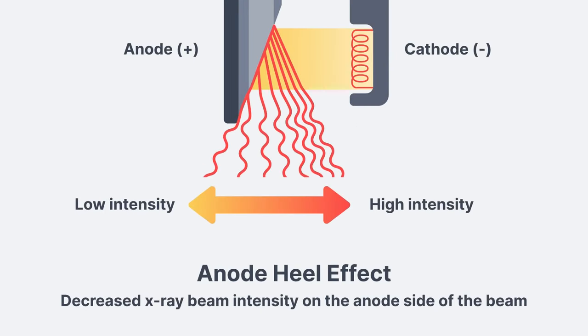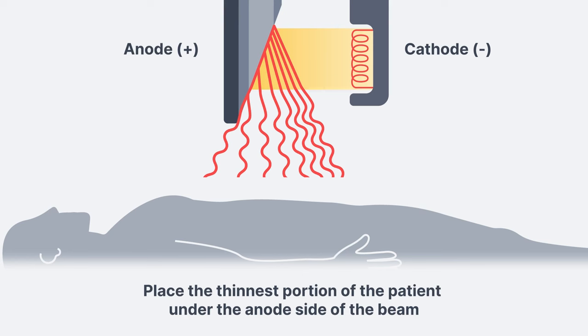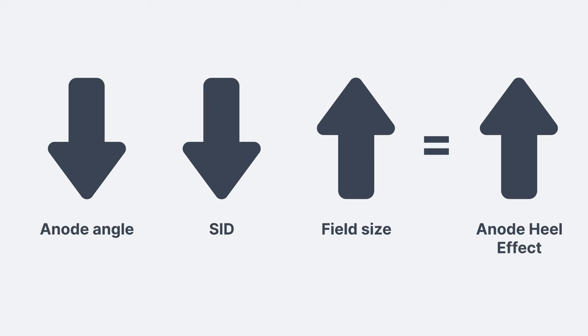In summary, the anode heel effect is the change in beam intensity across the length of the x-ray field. Specifically, the anode side has fewer photons and the cathode side has more photons — the anode side is weaker and the cathode side stronger. Remember that the anode heel effect can be used to our advantage by placing the thinnest portion of the patient under the anode side and the thickest part under the cathode side. Finally, three changes can increase the anode heel effect: first, decreased anode angle; second, decreased SID; and third, increased field size.